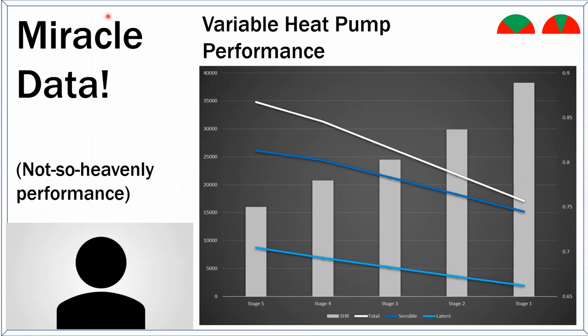So if I ran everything at 100%, at full capacity, and then at let's say low capacity, I was running the compressor at 50%, but I was running the fan at 60% or 65%, what would that do for me? Well, in the SEER testing, it would tell me that this has a higher SEER rating. The EER wouldn't be helped, but the SEER rating would. And everybody wants a big SEER rating, and so they design these things to do that.